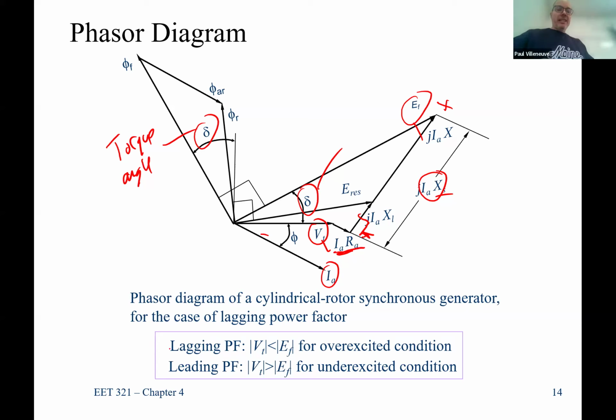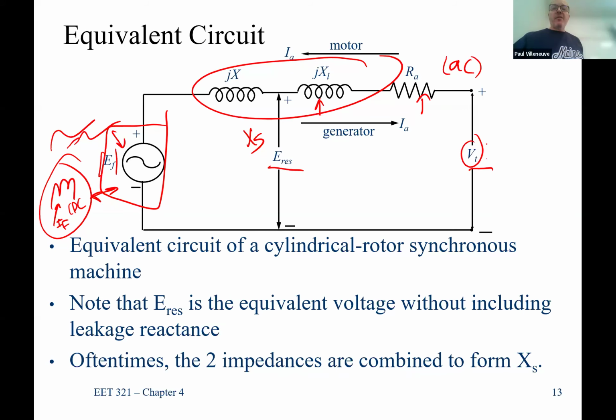This image shows a lagging power factor because the current lags the terminal voltage. If it was leading the terminal voltage, it would be up over here someplace, and our system would look quite a bit different. We'd also find, important for understanding operation, your terminal voltage is going to be less than your field voltage in the overexcited case, which means we're dumping vars to the system. The opposite under leading power factor, or when we're absorbing vars, our terminal voltage is going to be greater than our field voltage. Why? Because if this voltage is higher than this voltage, Q goes in here, but P is always out.